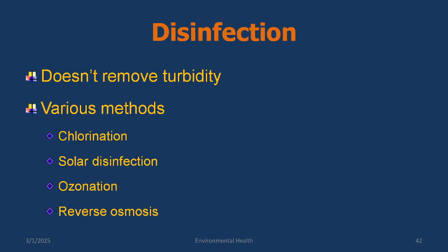So next step is disinfection. Disinfection does not remove turbidity. This is a very important fact which I have given you. Why? Because many people try disinfection at homes or at a smaller level also, without taking care of the previous two steps, that is sedimentation and filtration, then disinfection will not work at all.